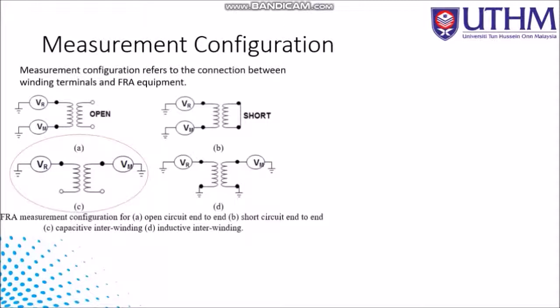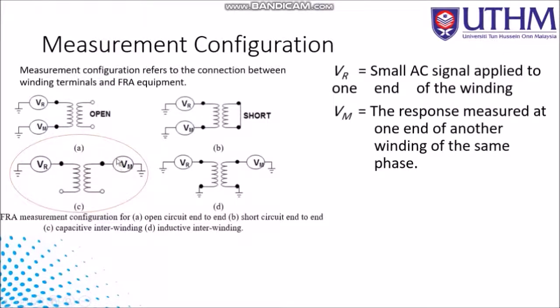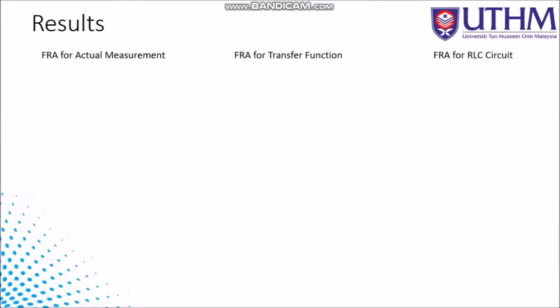The measurement configuration refers to the connection between winding terminals and FRA equipment. There are four measurement connections: open, short, capacitive, and inductive interwinding. In this study, we use capacitive interwinding. The measurement involves injecting a small AC signal to one end of a winding and measuring the response at one end of another winding of the same phase. This test configuration checks the response due to the influence of the space between the windings in the particular phase.